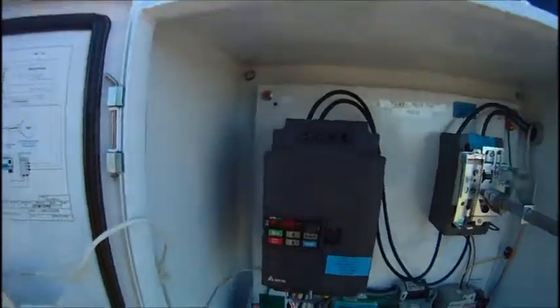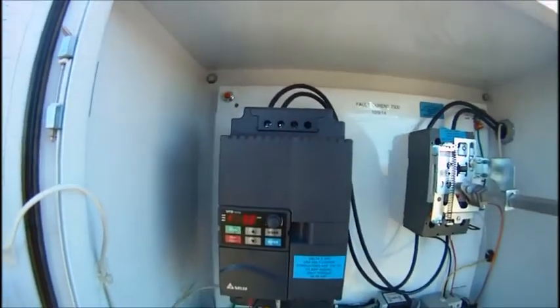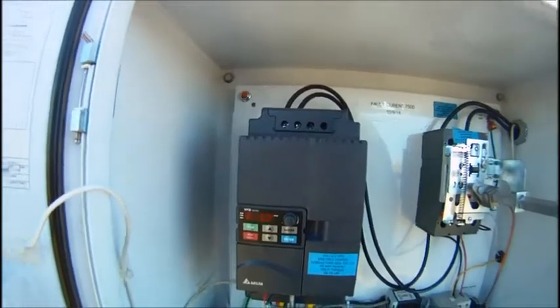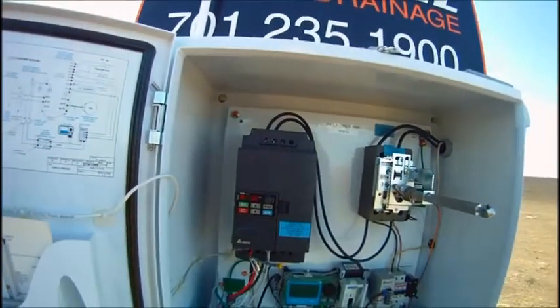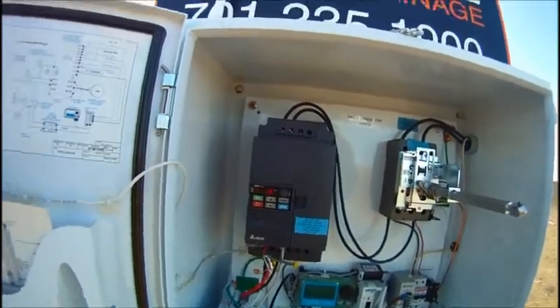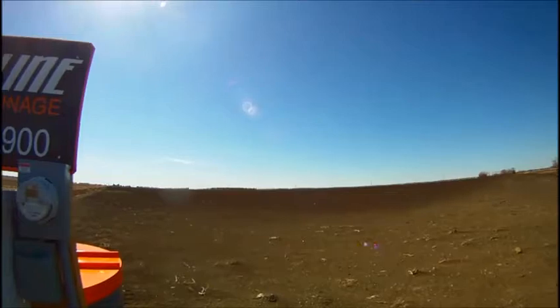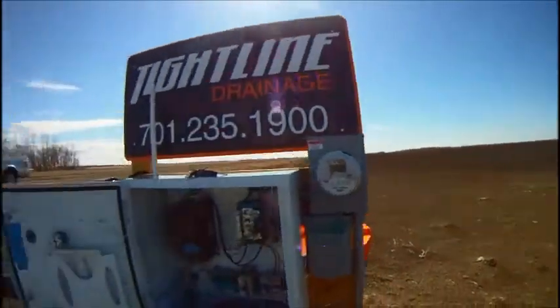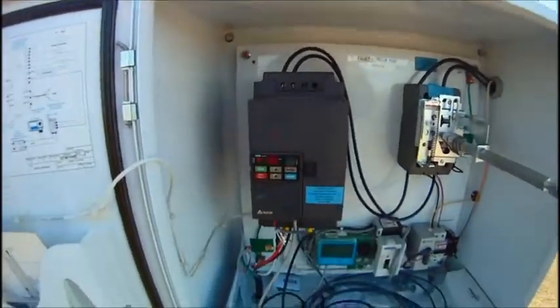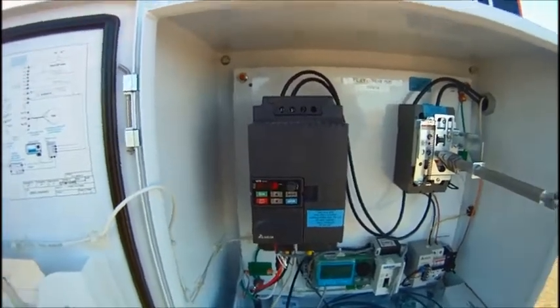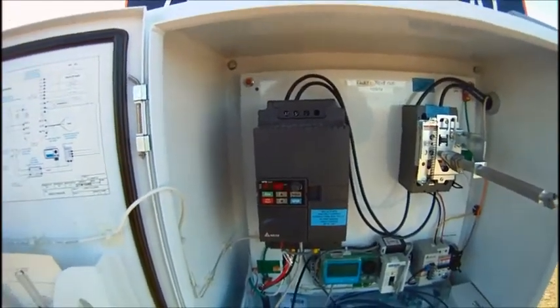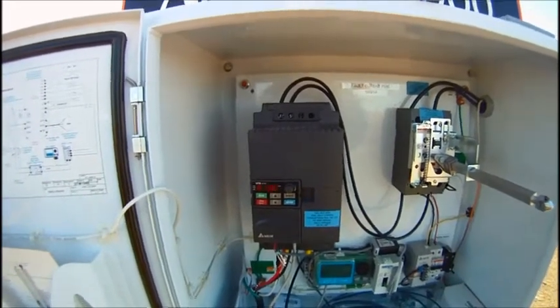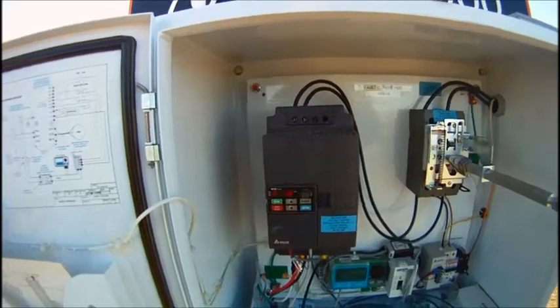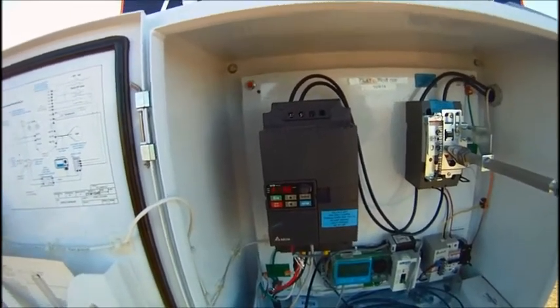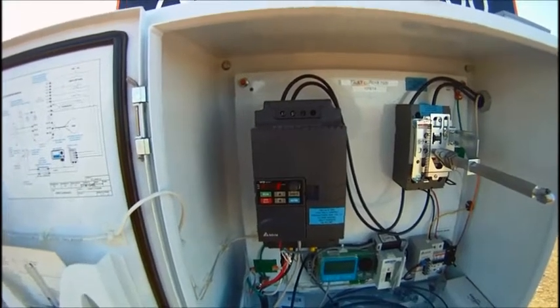So when you first turn your power on, you'll see where the set point is at. On this one, the date today is March 31st, 2015. They want to pump the field out now that the frost has come out, make sure that there's no standing water on the field at all. So they have the set point set way down right now. What we're going to do is bypass the set point and run this thing at full speed and clean out the air that's in the tube. So we will run the pump all the way down to the bottom of the transducer tube so air can be exchanged inside of that tube.